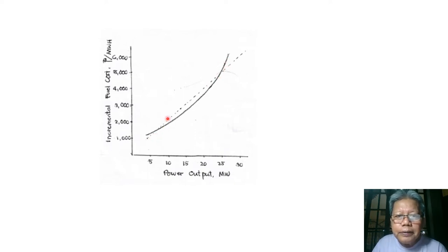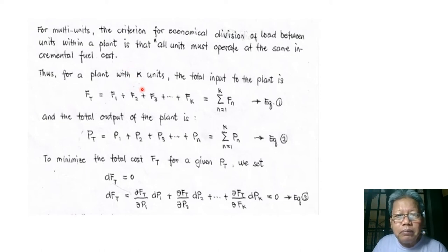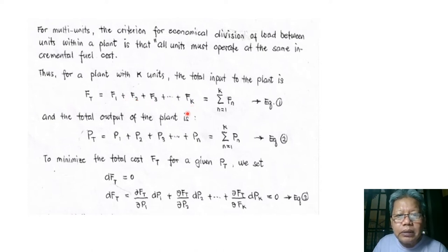Sometimes the incremental cost is represented by a straight line for simplicity. For multiple units, the criterion for economical division of load between units within a plant is that all units must operate at the same incremental fuel cost. Thus for a plant with k number of units, the total input or total cost is: F_T = f1 + f2 + f3 + ... + fk, which is the summation of f_n from n=1 to k.